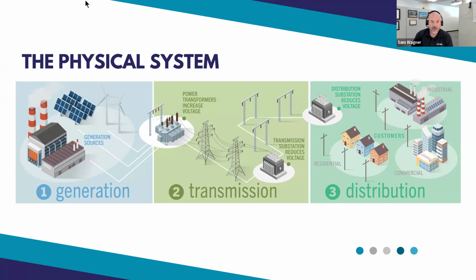Increasingly these days, there's a mix of above ground and underground, but eventually we have to distribute that power to the end use customer. We go through a series of smaller and smaller transformers, some of which just look like green boxes at the end of your cul-de-sac. For a home, we continually step that power down to the point where we're delivering it at 240 volts. So we're going from, say, 161,000 volts down to 240 volts to feed your house.